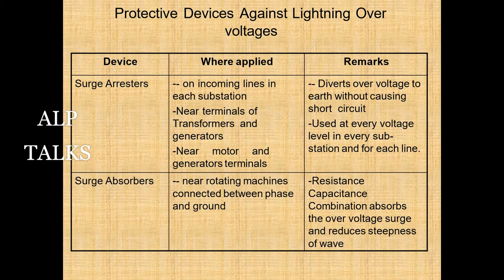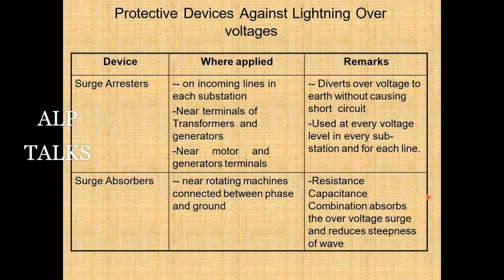Surge arresters are used at incoming lines in each substation, near terminals of transformers and generators, and near motor and generator terminals. They divert overvoltage to earth without causing a short circuit, and are used at every voltage level in the substation and for each line. Surge absorbers are also used near rotating machines — connected between phase and ground. The resistance-capacitance (RC) combination absorbs the overvoltage surge and reduces the steepness of the wave.